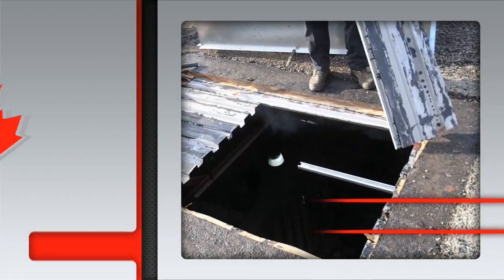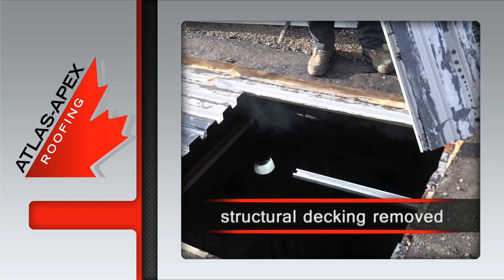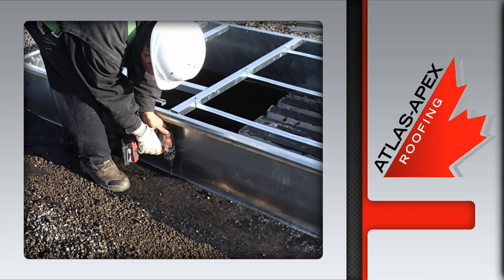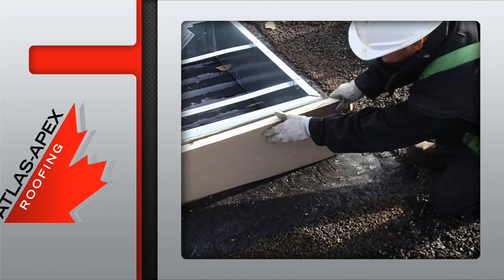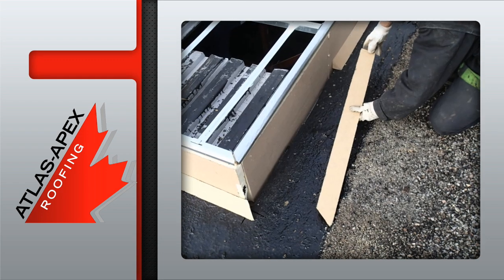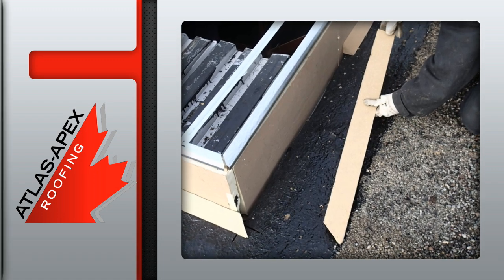A portion of the structural decking is also removed, providing clearance for the mechanical ductwork. The steel curb is then positioned into place and secured with metal fasteners. The skeletal frame of the steel curb is filled in with new polyiso insulation, followed by a fiber cant with mitered edges to ease the transition of the new membrane.